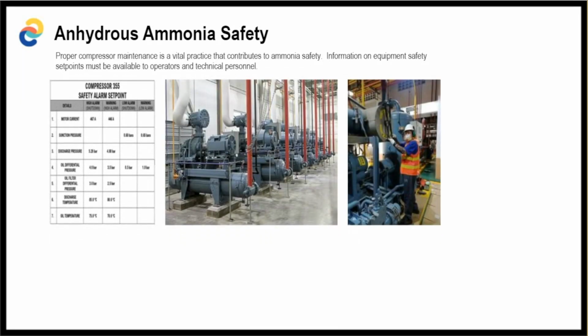For this slide, it shows the information of the equipment, the set points for the alarm, and also records of past faults should be kept. So it's sort of a history should there be some activities done to an equipment, to be recorded. And then also what actions, what solutions have been made to it. Monitoring should be done to ensure that equipment on the plant is within permissible operating conditions. So the settings.